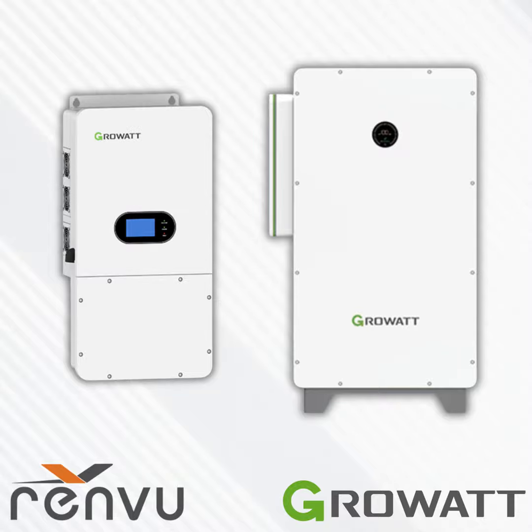And Tyler mentioned these are also outdoor rated, dust-proof, waterproof, 5 kWh modular design, and you can stack these as well as having multiple stacks and multiple banks up to 160 kilowatt hours per SPH inverter. And you could again have up to 6 of the inverters in parallel. These ALP batteries, in addition to UL 9540A, also have the optional wall mount bracket, which is also included in the UL 9540A certification. So for certain applications where there may be spacing or space limitation requirements or lack of fire suppression indoors, you could use wall mount brackets as an alternative option.